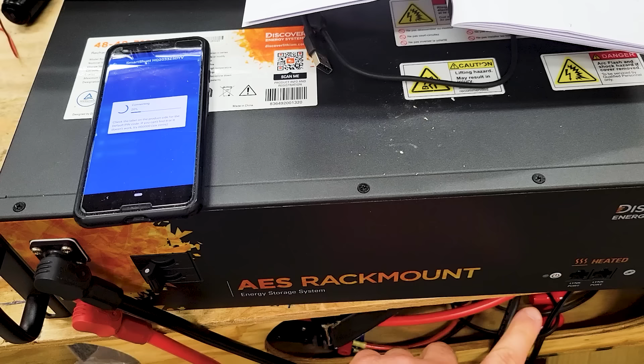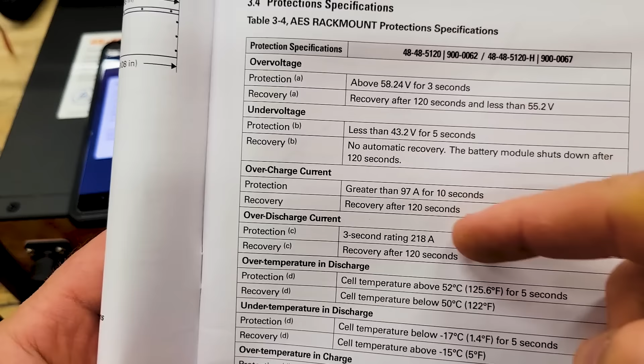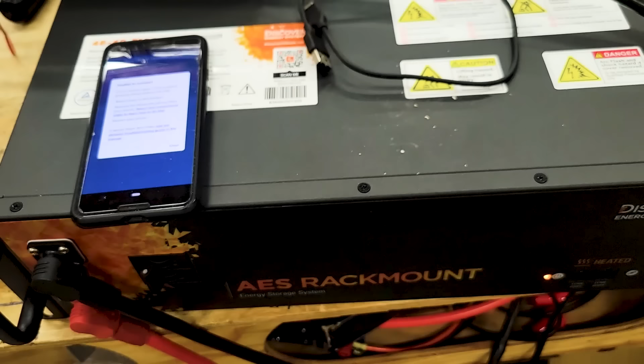And it shut off. There's a flashing amber light, and we're going to find out if this will turn on automatically. So in the manual, it says for over discharge current, we have a recovery after 120 seconds. So 2 minutes, and we'll see if it does do that. At this point, we're more than 2 minutes, and it's not the BMS that tripped. The BMS is still running. It's the circuit breaker that tripped off, and so this is letting us know that the circuit breaker's off. So let's try this again with a little bit less current and see how long it takes.